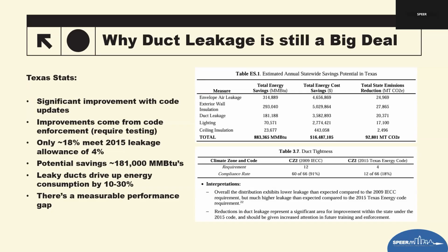We did a survey, a field study, a while back, and this is some of the pieces from that. One of the most telling stats is that only about 18% of the homes built to the 2015 Texas Energy Code, back when we did the study, met the required 4% duct leakage. That means more than 80% of the homes were missing the mark. If you look at this, you can tell we had several that were not actually meeting that when the study was done for the 2015.